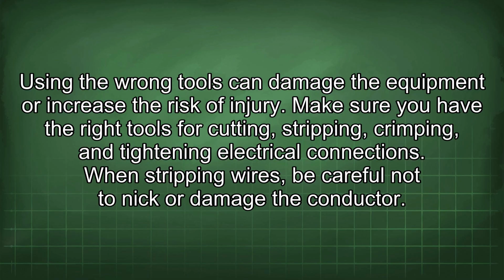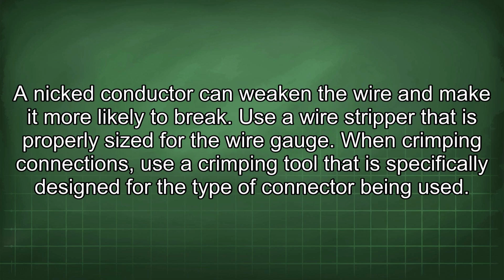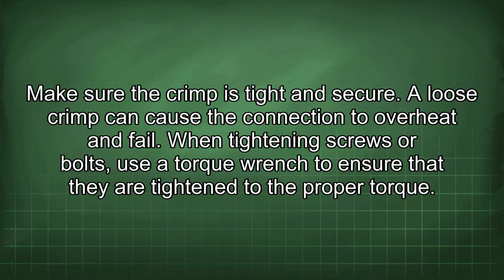When stripping wires, be careful not to nick or damage the conductor. A nicked conductor can weaken the wire and make it more likely to break. Use a wire stripper that is properly sized for the wire gauge. When crimping connections, use a crimping tool that is specifically designed for the type of connector being used. Make sure the crimp is tight and secure. A loose crimp can cause the connection to overheat and fail.